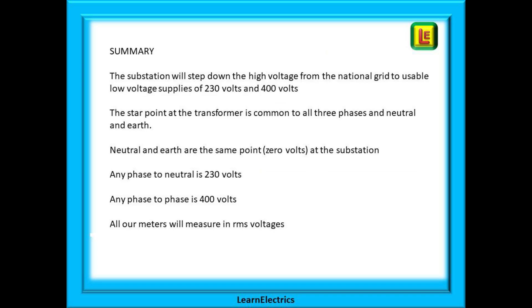In summary then, the substation will step down the high voltage from the national grid to usable low-voltage supplies of 230 volts and 400 volts. The star point at the transformer is common to all three phases and neutral and earth. Neutral and earth are the same physical and electrical point, zero volts at the substation. Measuring any phase to neutral is 230 volts and any phase to phase is 400 volts.